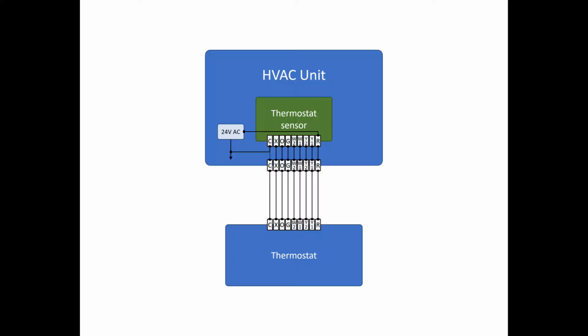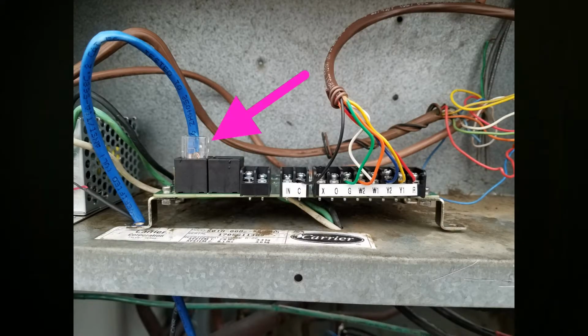You'll also want to connect the common wire. However, some units don't have a common wire. In this case, you want to connect the thermostat sensor common wire terminal to the 24-volt AC power supply of the HVAC unit. Lastly, run the Cat5e or Cat6 cable to the thermostat sensor and then close up the unit and turn it back on.